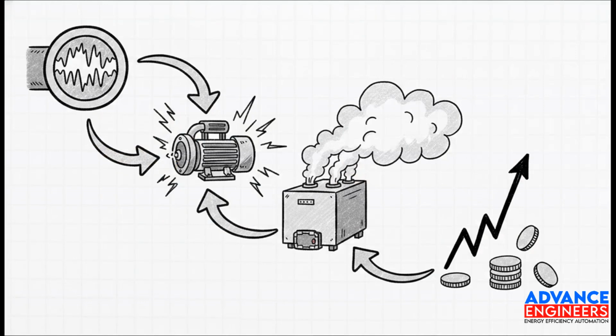And this creates a vicious cascading cycle of failures across your whole facility. Because your heat transfer coefficient, or U value, drops, your system tries to compensate by demanding way more steam, so now you've got longer heating cycles. On top of that, the scale physically narrows the hydraulic paths inside the tubes, which jacks up the friction, forcing your pumps to work significantly harder and draw way more power. Before you know it, you're looking at unplanned production drops, nasty bottlenecks, and utility bills that are absolutely skyrocketing.